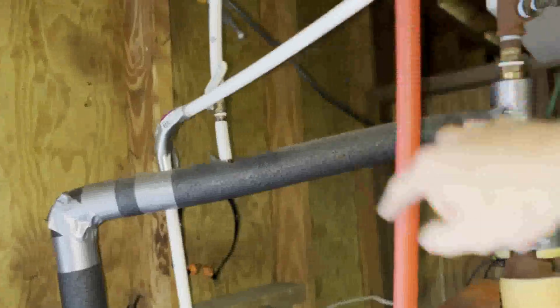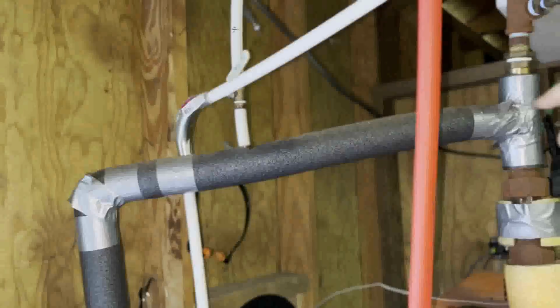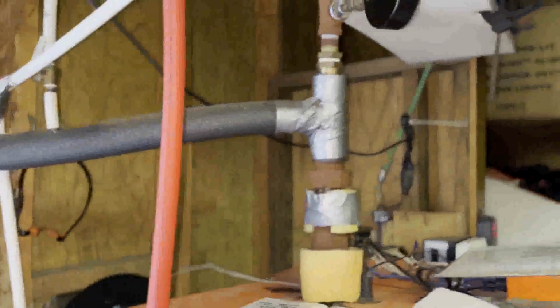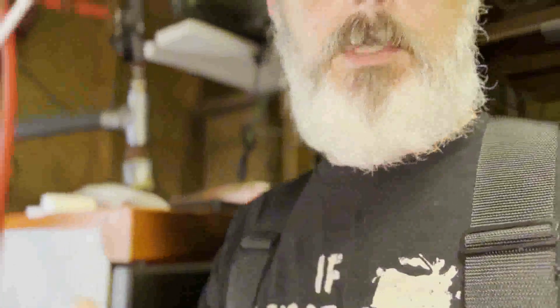So basically, when 120 goes, this is dead. There's no 120 going into the transformer, thus no line voltage to control this unit. So this will go blank. It'll go dead. But when I lose power, that gets back to that guy being powered closed. As soon as 120 goes away, the spring will open that, and that will open a dump zone. So basically, it'll thermosiphon up. Hot water will rise, come over, and fall just like that. And it'll do that on its own. Thermosiphon dump zones have been around a long time.